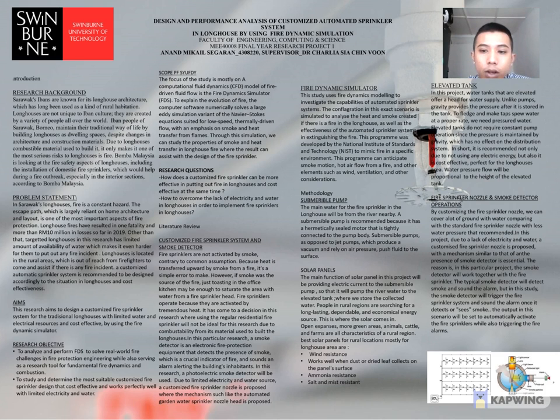So when the smoke detector detects the smoke, it will activate the fire sprinkler directly. In this particular way, the fire sprinkler system design is very efficient and effective in handling fire threats or situations in longhouses due to the extremely combustible hardwood materials. Smoke detectors respond faster than residential and conventional sprinklers, according to all the studies, and thus provide the earliest warning of a fire to building inhabitants.